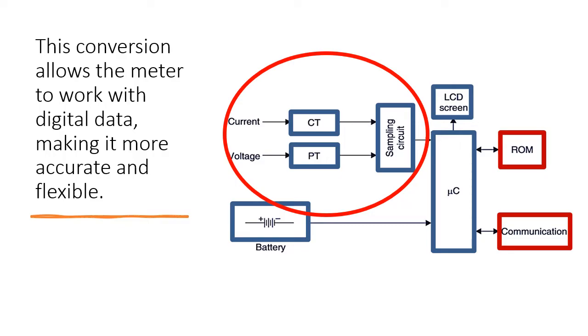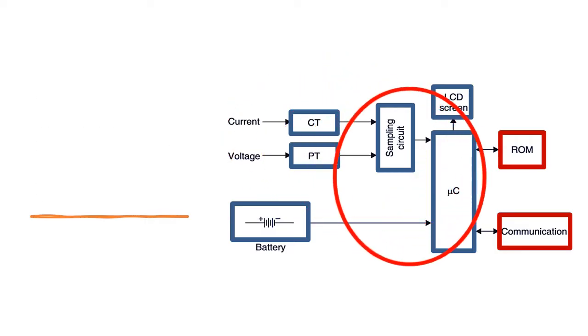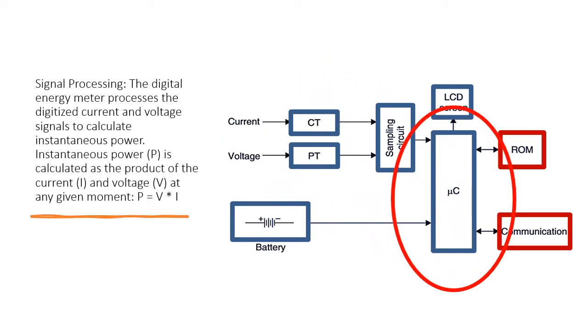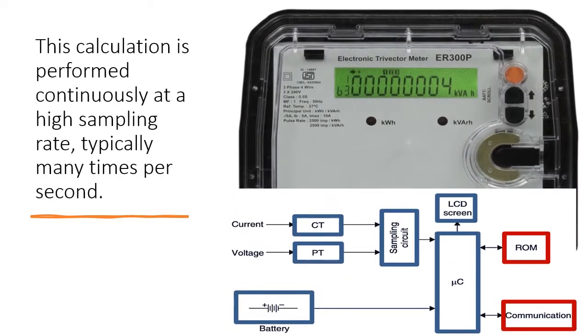The digital energy meter processes the digitized current and voltage signals to calculate instantaneous power. Instantaneous power (P) is calculated as the product of the current (I) and voltage (V). At any given moment, P equals V times I. This calculation is performed continuously at a high sampling rate, typically many times per second.